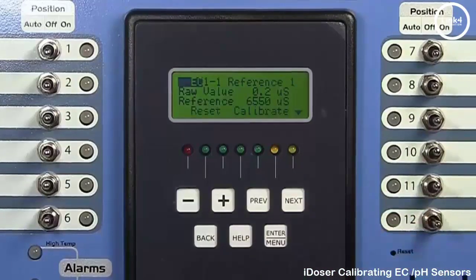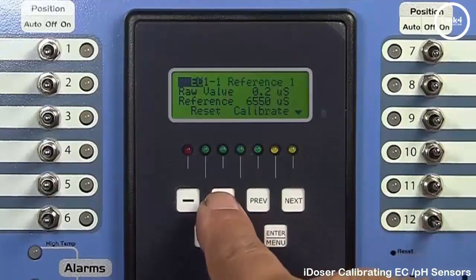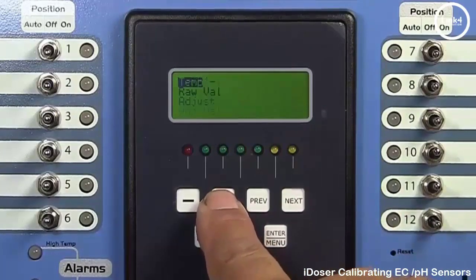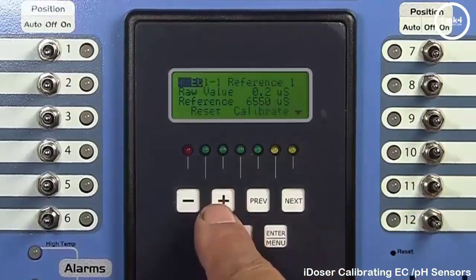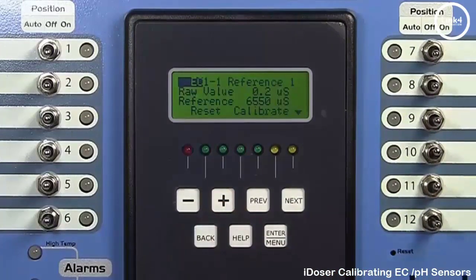Hit Enter Menu. Now on the calibration screen, the first field we come to is the sensor we want to calibrate. Hit plus or minus allows us to navigate through the different sensors. And we want to go ahead and leave EC highlighted because that's the first sensor we're going to work with.